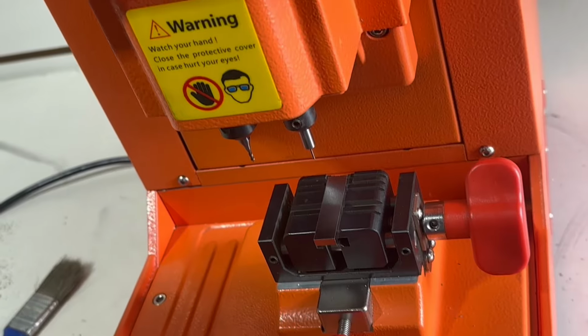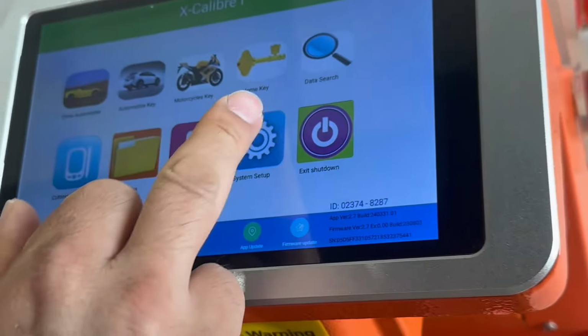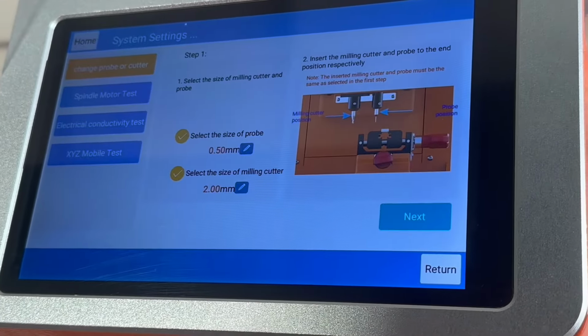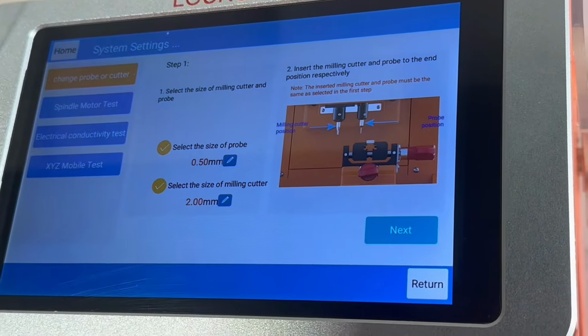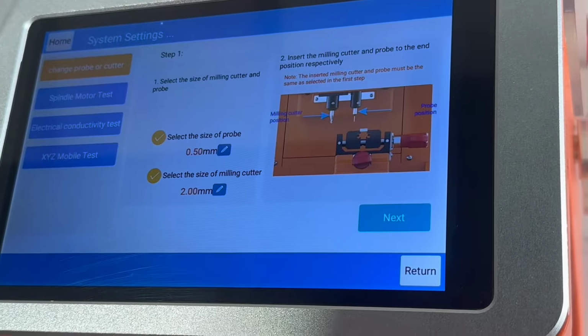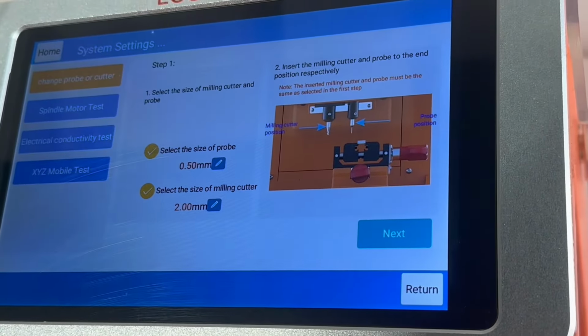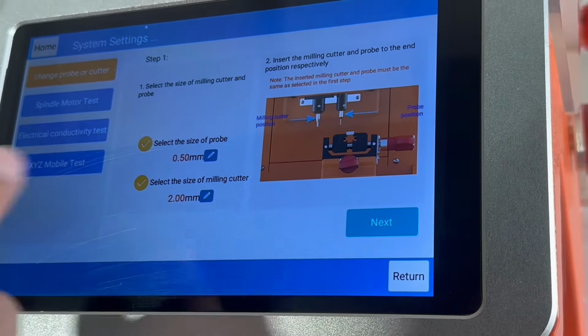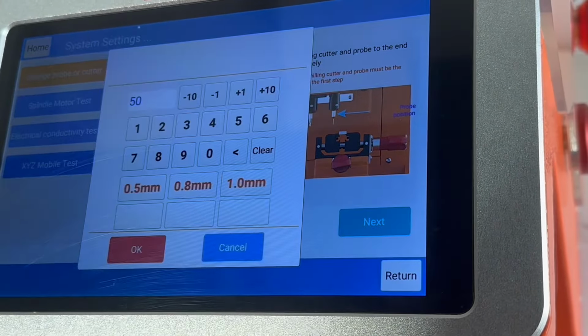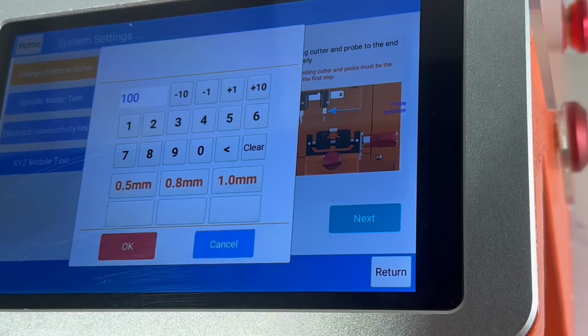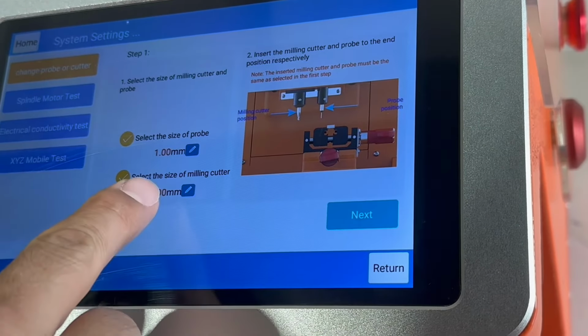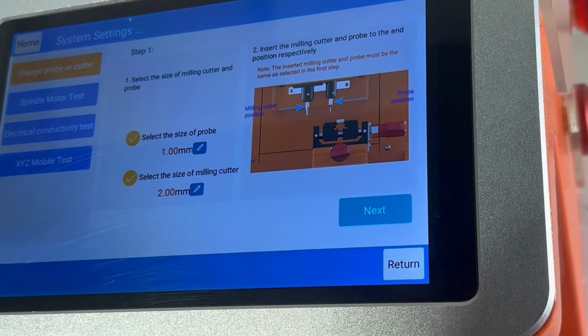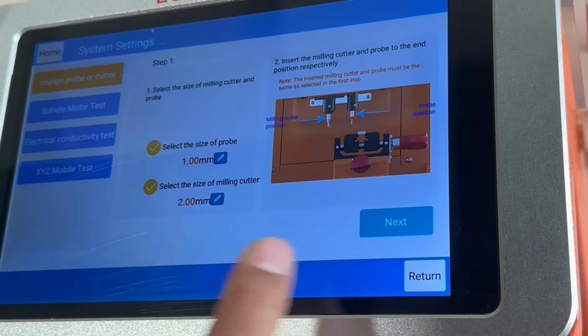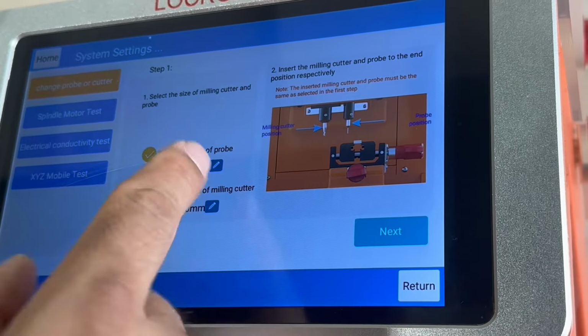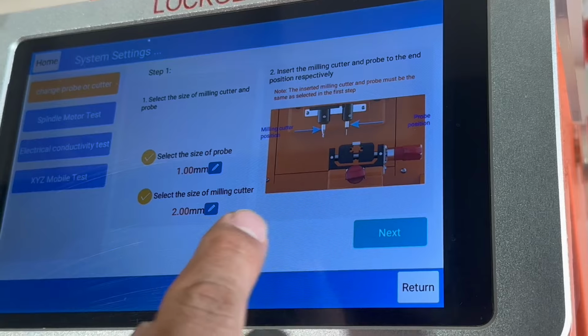So now we're gonna start. So you have to go to the setting, system setup, and the first line here, and then it will tell you what you have to do. So since we put the 2mm milling cutter and the probe 1mm, we're gonna change this one to 1mm, the probe. Okay, and 2mm is already there, so we don't need to change. Next, it says insert those. We already did in the previous step.